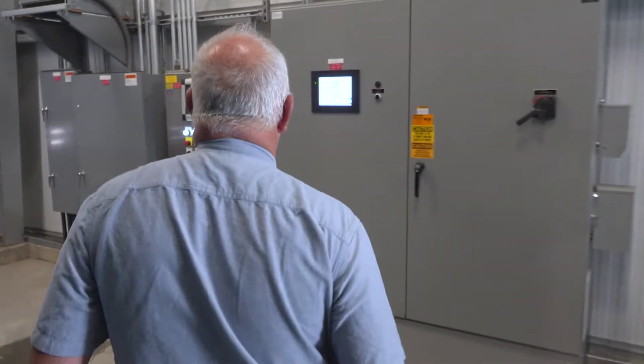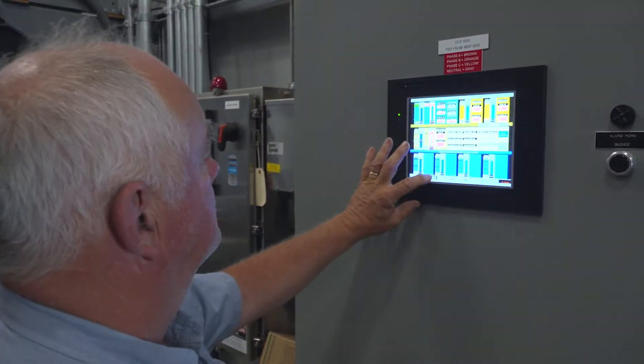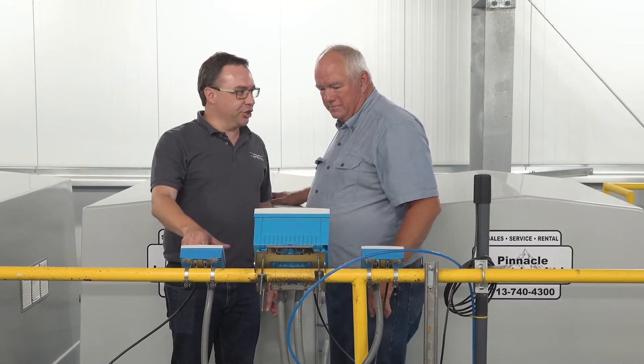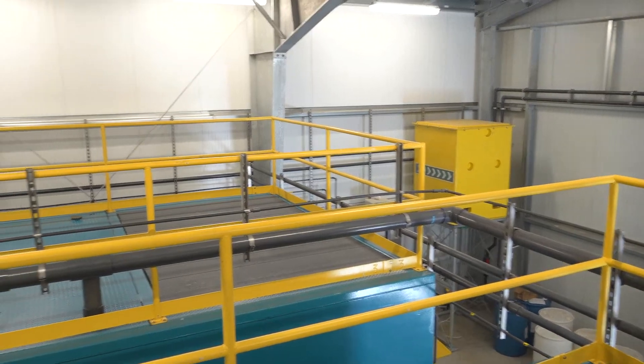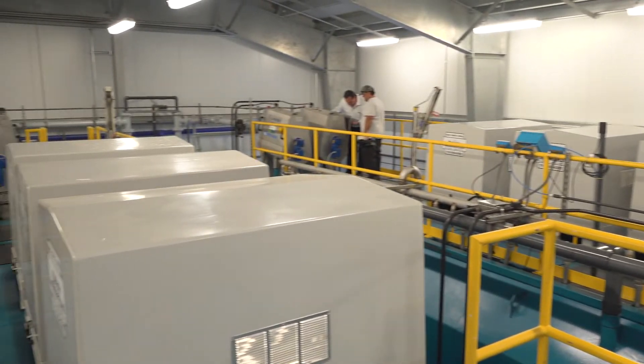I'm Bob Claudefelter. I'm the Director of Operations for Treatment Technology. The membrane bioreactor process — from the first day, the effluent will noticeably be better. BOD and total suspended solids are below the detection limit. That's unusual. Normally, this facility would operate in the mid-20s to maybe below 30 mg per liter for those two constituents.